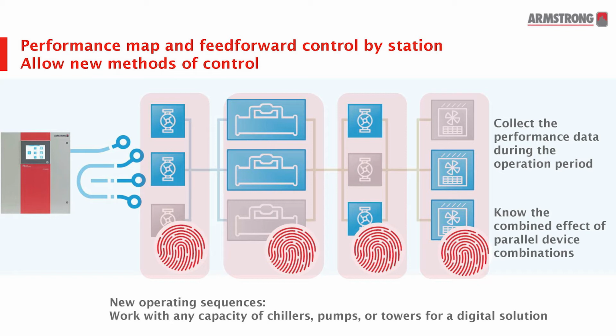As any one piece of equipment starts to change, it affects the productivity of that equipment station. If there are 3 pumps operating in parallel and we find one starting to degrade, it shows that combination of equipment isn't ideal, and maybe we want to use the other 2 pieces of equipment a little longer before bringing in the deficient one. It also lets us ask how much capacity we have now that one of those 3 pieces of equipment is in a degraded state, and how much capacity we have from that station. So when we talk about the design day flow requirements of the cooling capacity required, we know what we can do.